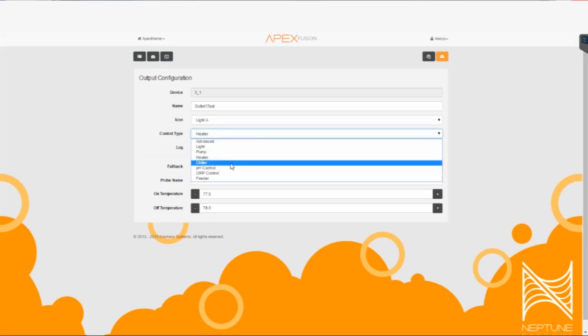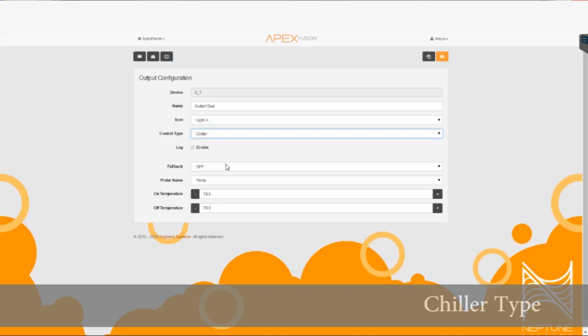Let's go over to the chiller control type, which is very similar to the heater control type. Both have fallback modes and probe selection, letting you turn on the outlet based on different temperature readings or ranges. By default, the on temperature is 79 degrees when the water gets warm, turning off once it hits 78 degrees.